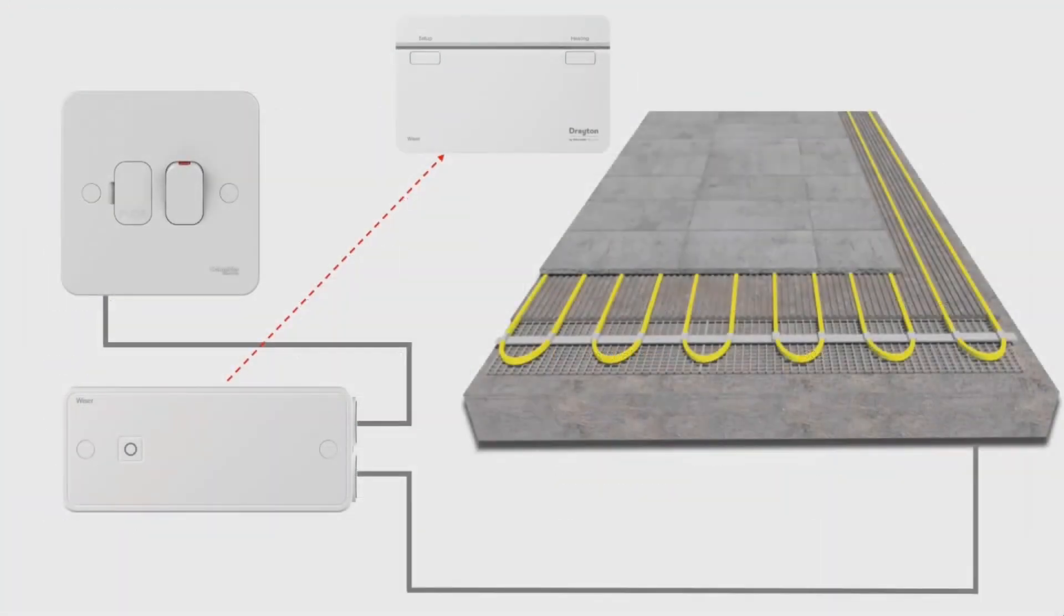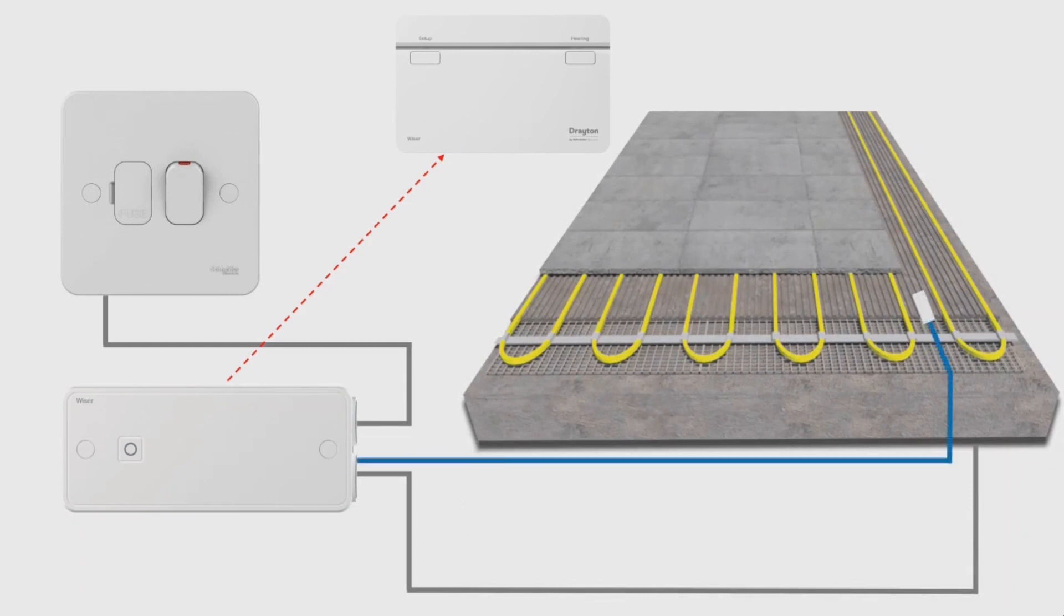For electric or dry underfloor heating, the method of connecting the load is exactly the same through the electrical heat switch, but you now need to use our room floor sensor buried within the floor to ensure that if a fault develops the floor can't overheat.